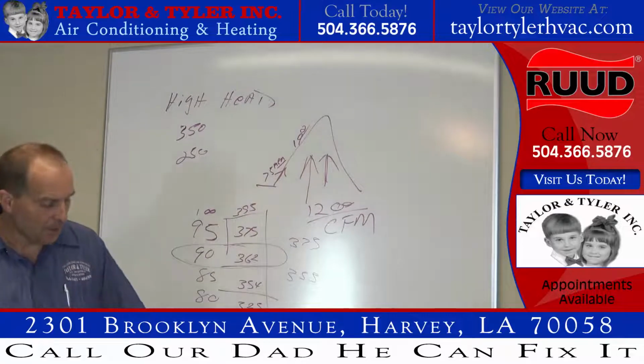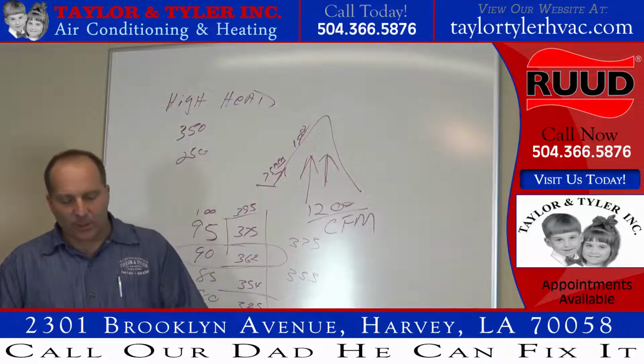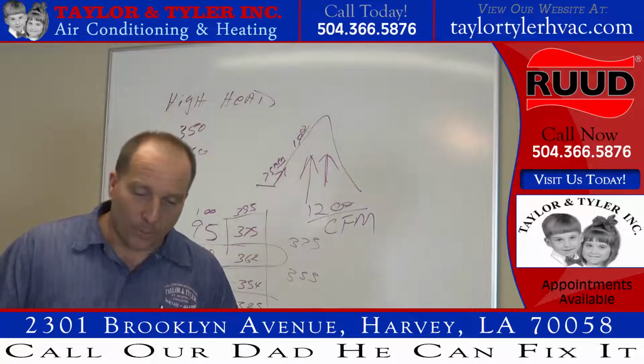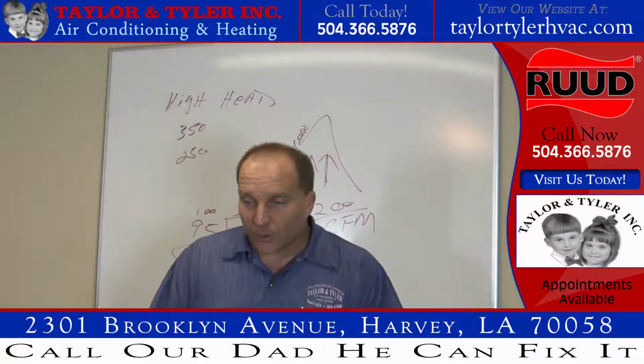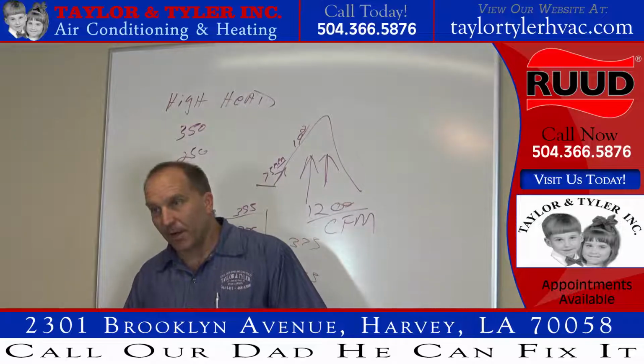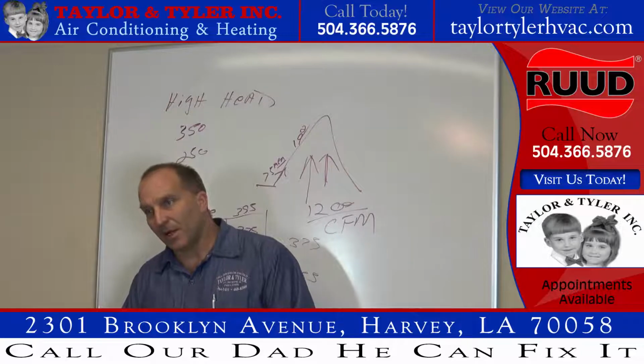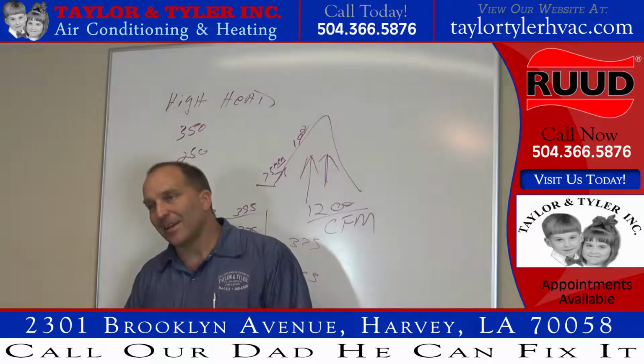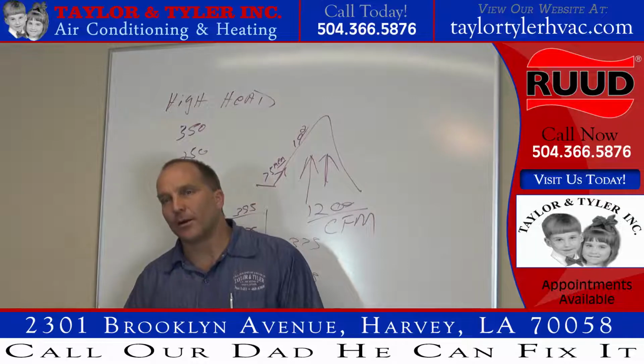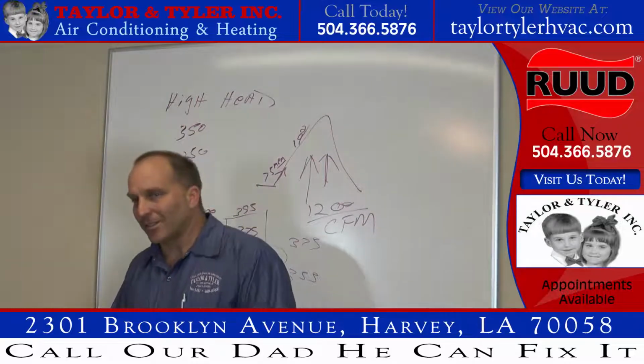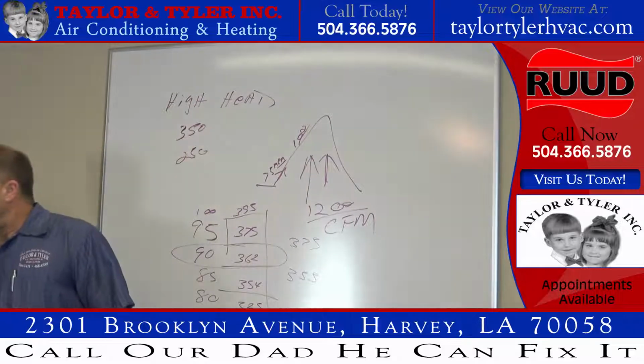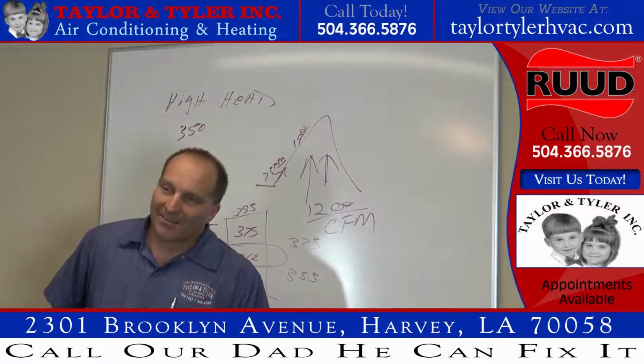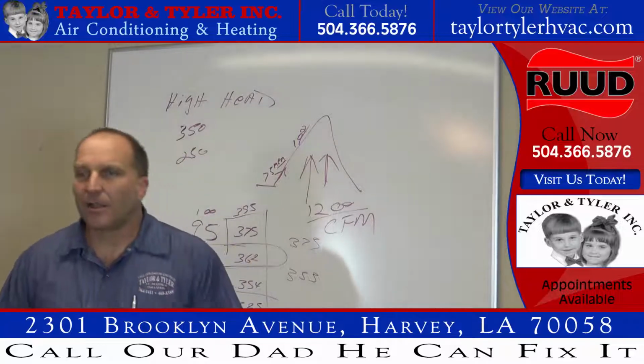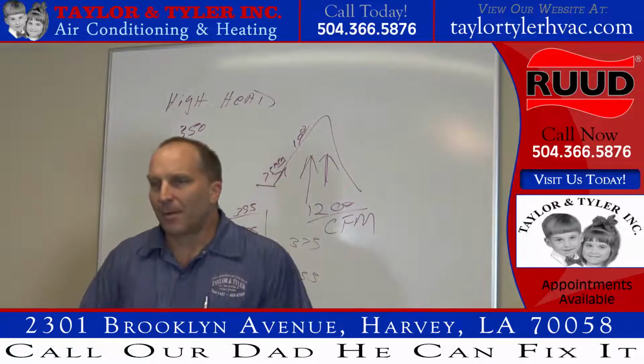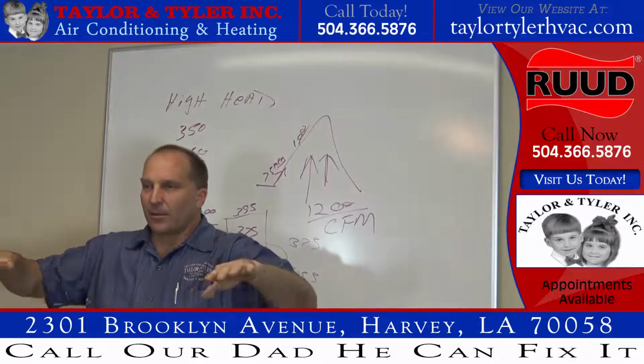Okay? Alright. Mild refrigerant restrictions. Now the difference between a mild refrigerant restriction and a major refrigerant restriction is enormous. You go put a gauge on the system, it's turned off and your pressures are equalized, high and low side are equalized. Let's just say in this case I have a major restriction in my dryer on my high side line. Now watch how this works. You turn that system on, and I have a restriction in my high side line in the dryer.